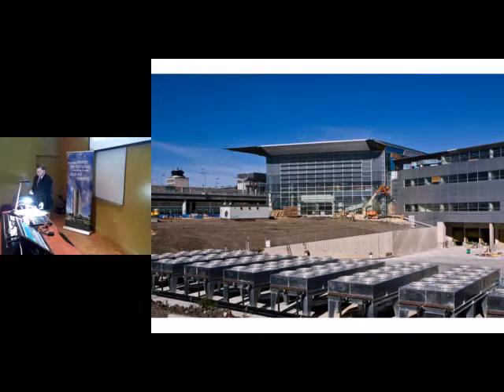What's even more remarkable is on the cooling side. When we put the radiant floors on this past summer and really gave them a good solid test, we found that basically we could cool the entire building with the radiant floors alone. We didn't need to do any air treatment apart from whatever fresh air is coming into the building and being treated from outside air conditions. The chilled water system coupled with the radiant floors is in fact so powerful that you can very much overcool the spaces. We actually had one area where it got down to about 10 degrees Celsius one night just on air conditioning, and it was 35 degrees Celsius outside. So it was basically a meat locker.